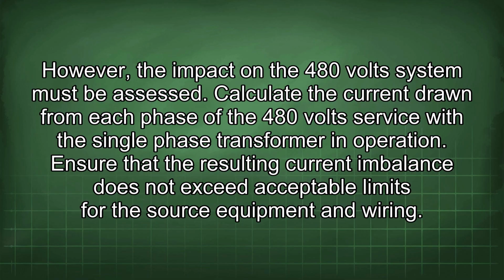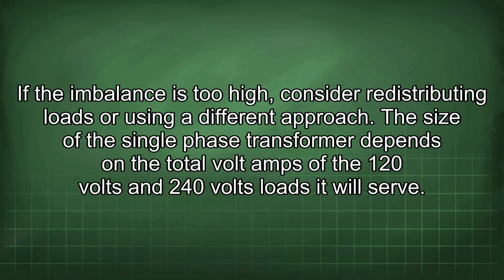Calculate the current drawn from each phase of the 480 volt service with the single-phase transformer in operation. Ensure that the resulting current imbalance does not exceed acceptable limits for the source equipment and wiring. If the imbalance is too high, consider redistributing loads or using a different approach.